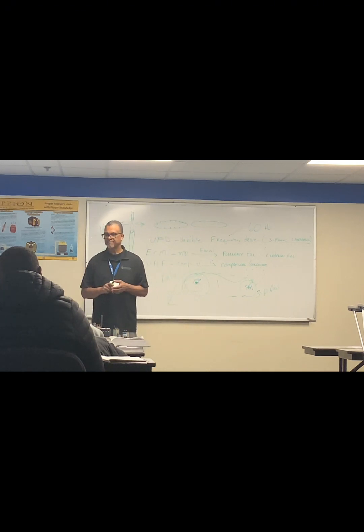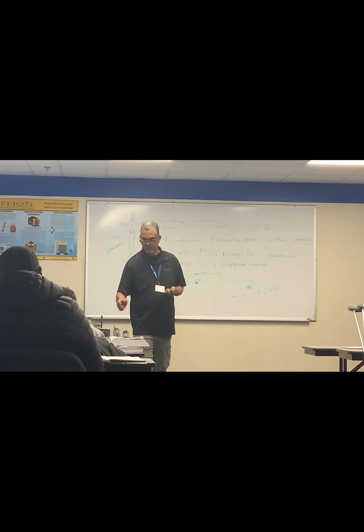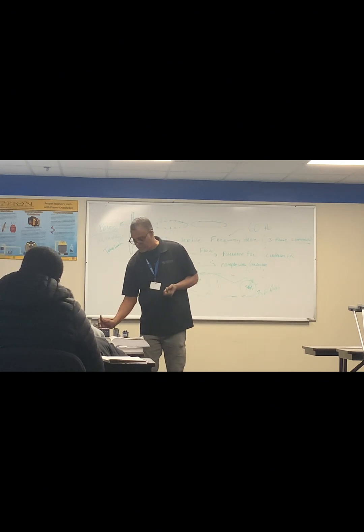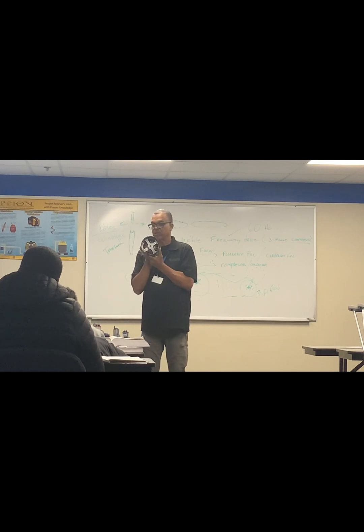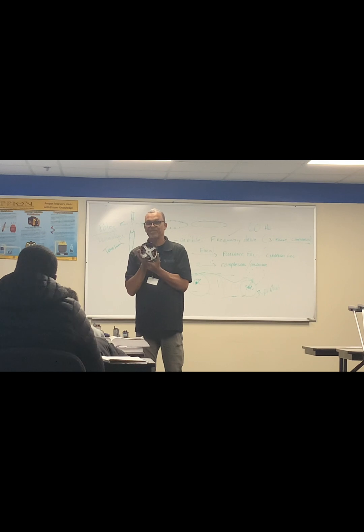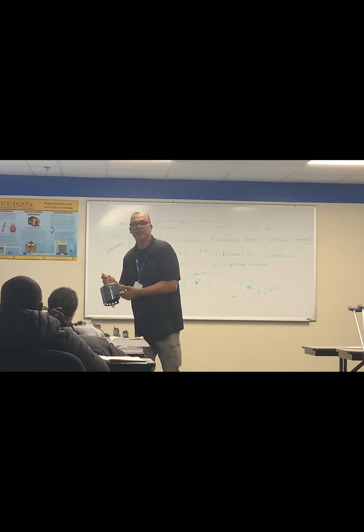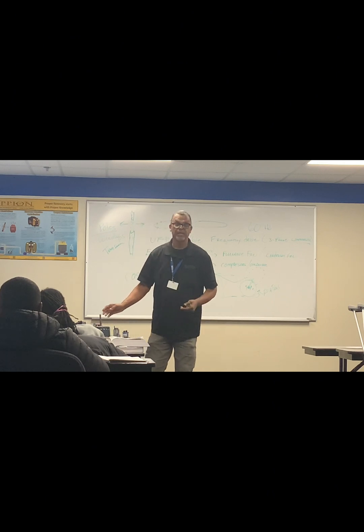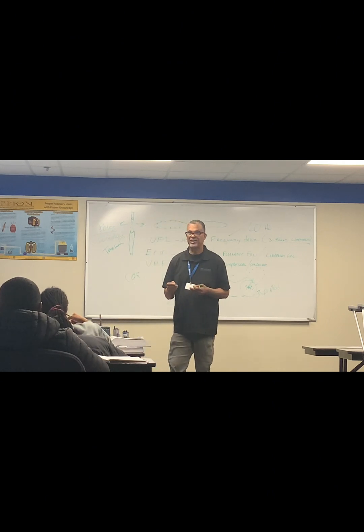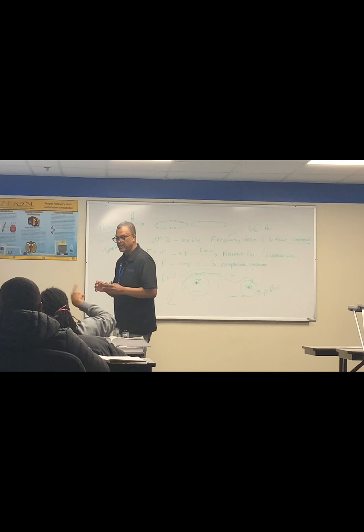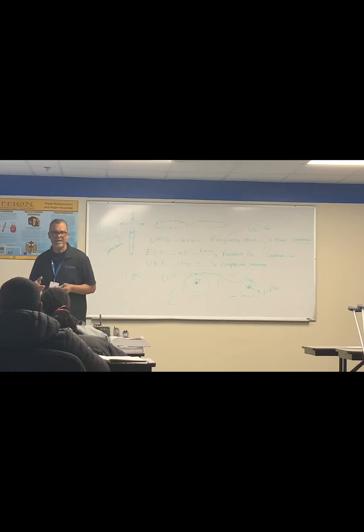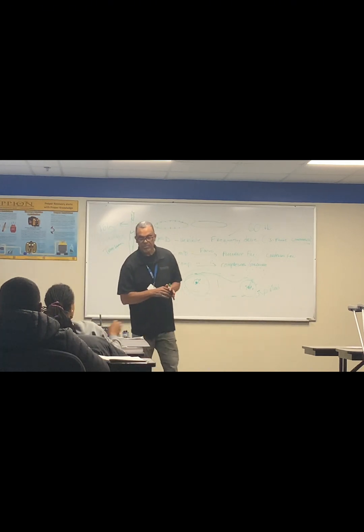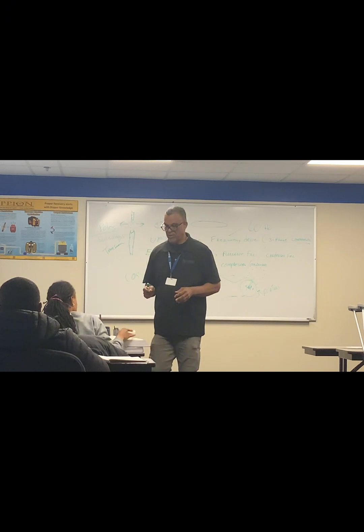Yes. Can you show us with the pole? Well, this one is different, but the poles are in there. That's a variable speed motor though. So since it has a lot of speeds and the poles represent speeds in an older type motor, it would have maybe 6 or 8 poles in the bottom of it. And I think it gives a good drawing of the poles in your book.